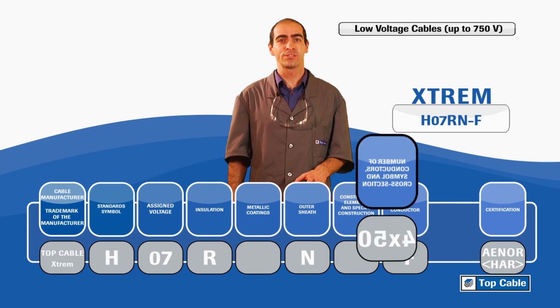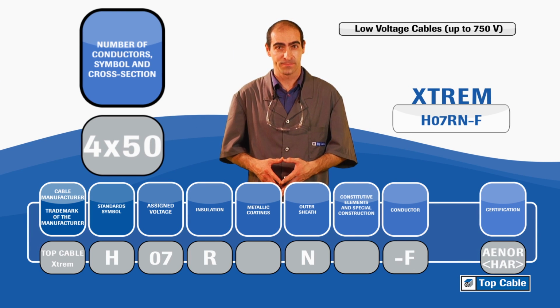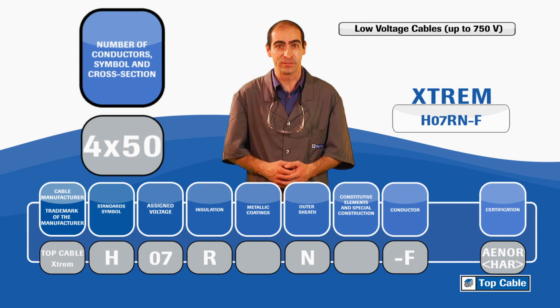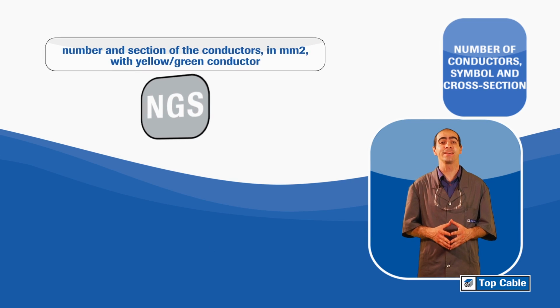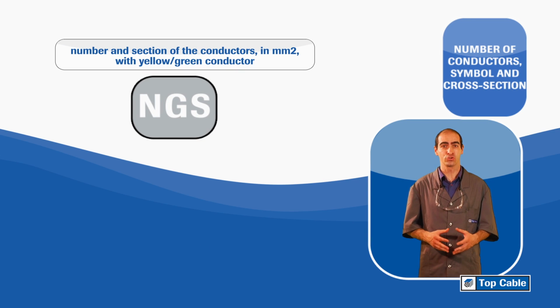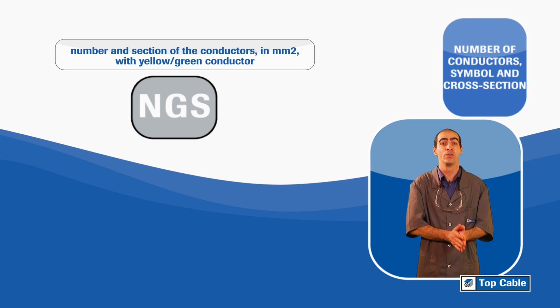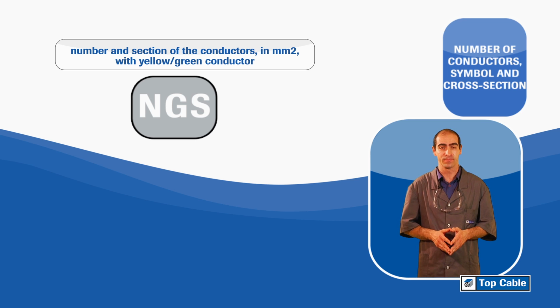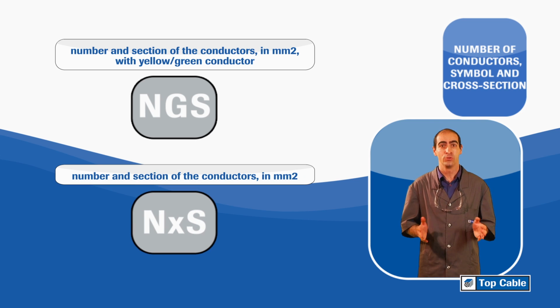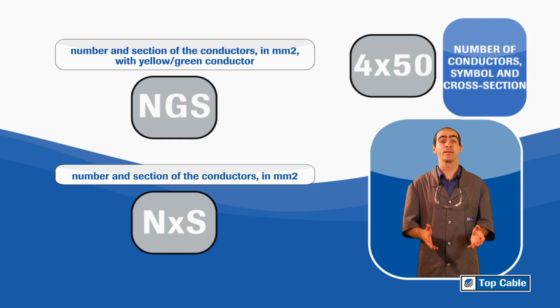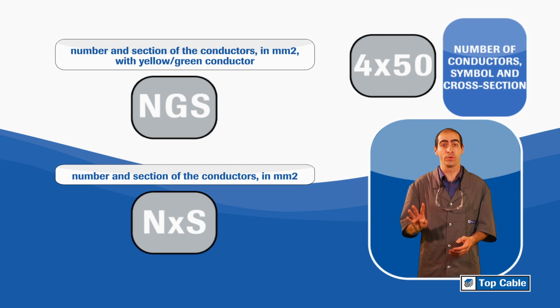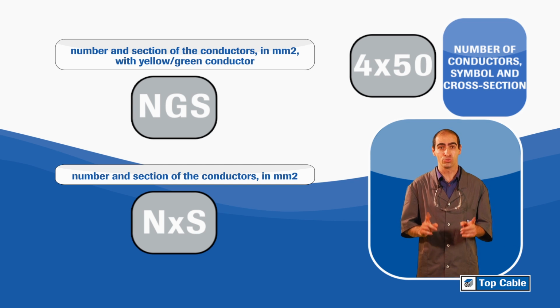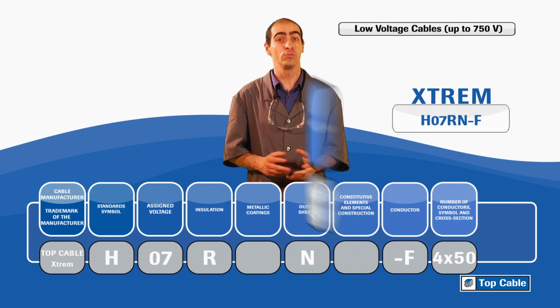The next section details the number and section of the conductors. The section is expressed in millimeters squared. NGS, number and section of the conductors in millimeters squared, with yellow-green conductor. NXS, number and section of the conductors in millimeters squared. In the example, 4x50 indicates that it has 4 conductors of 50 millimeters squared, without a yellow and green conductor.